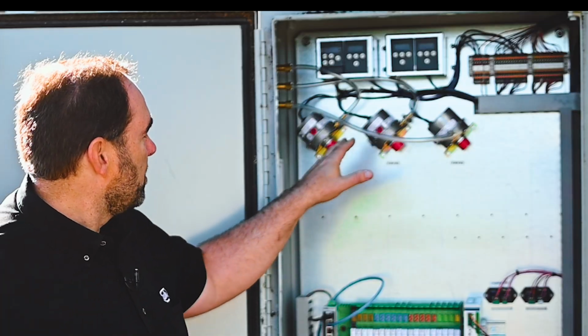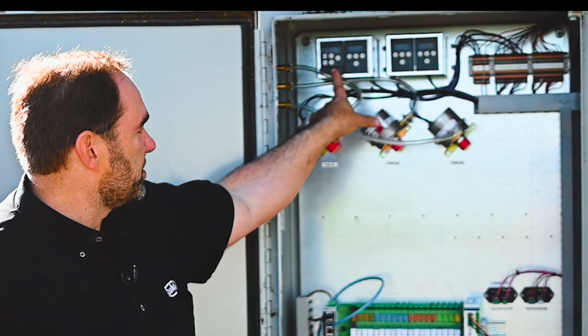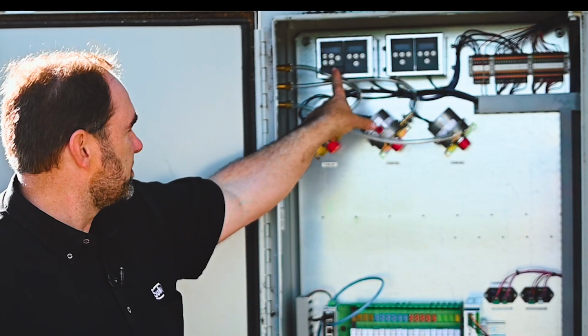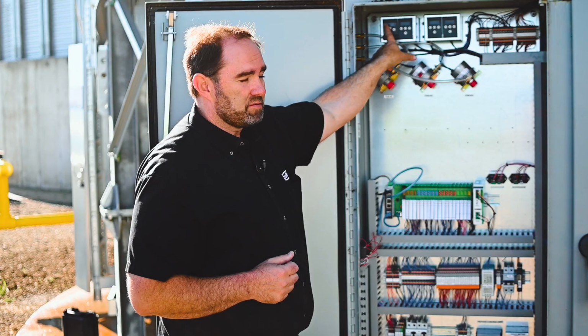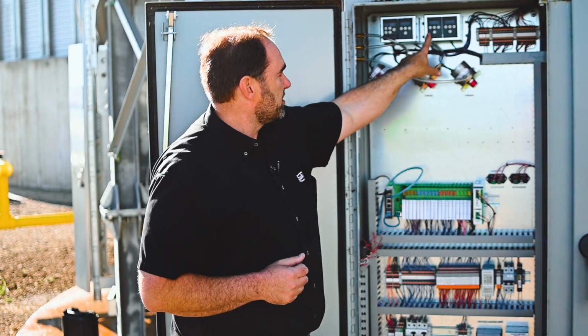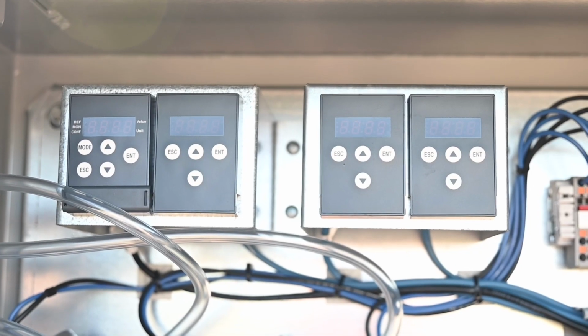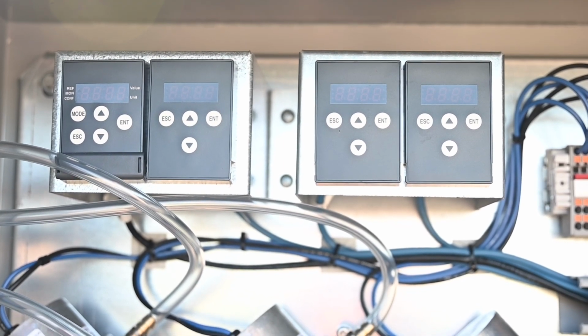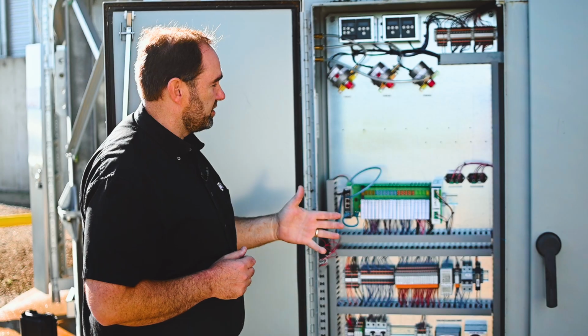We'll start at the top. We have some remote displays. The first one is going to be for the unload VFD. So that's going to show either hertz or amps, whatever we have it set at. And then we have 3 displays for the fan soft starts on there. So we can see these without having to get into the high voltage component on the right side.